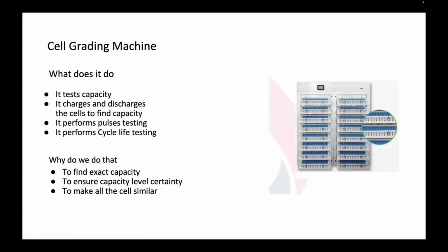This is done to find the exact capacity, to ensure the capacity level, and there is a unique feature in this machine. Once you charge and discharge all the cells, this machine normally comes in 512 channels, and based upon the capacity of the cells, you can give the command from your computer. The similar cells will have the light glow on the same type of cells, so you can take out those cells first since they are of the same capacity. This is how the cells are normally graded on this machine.